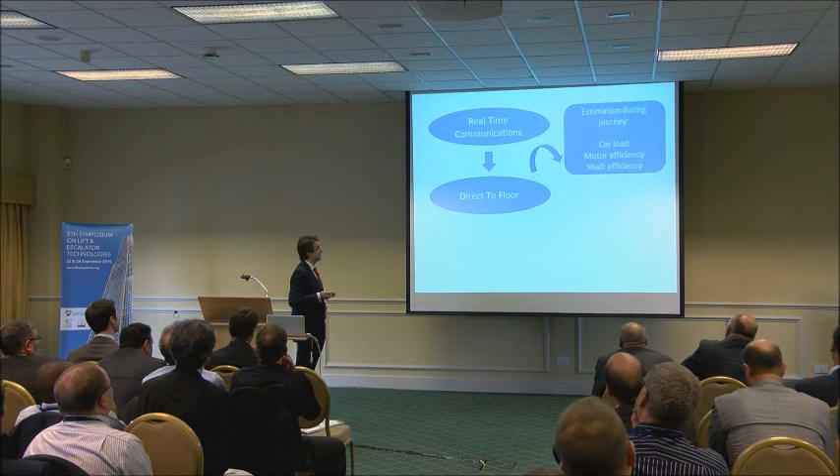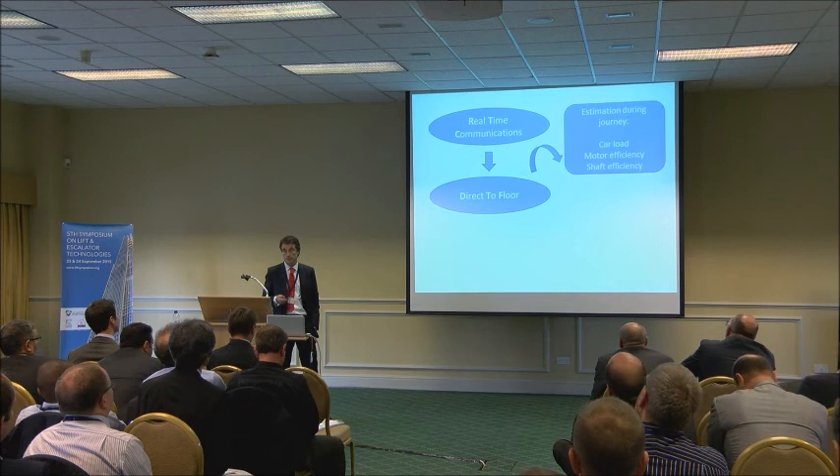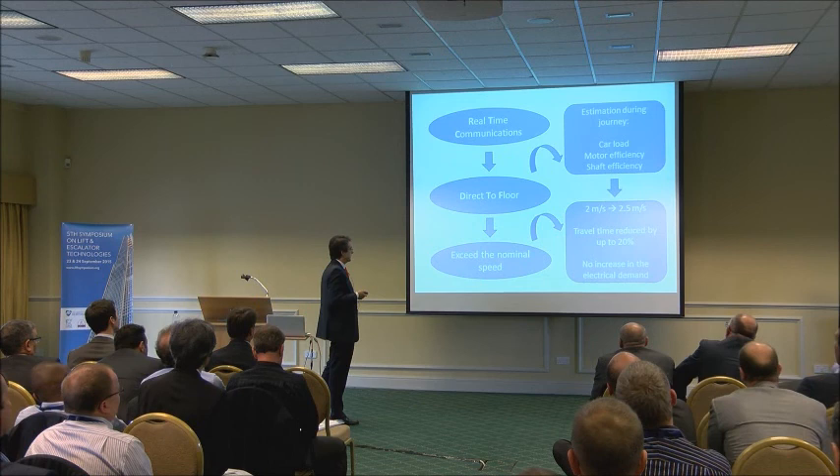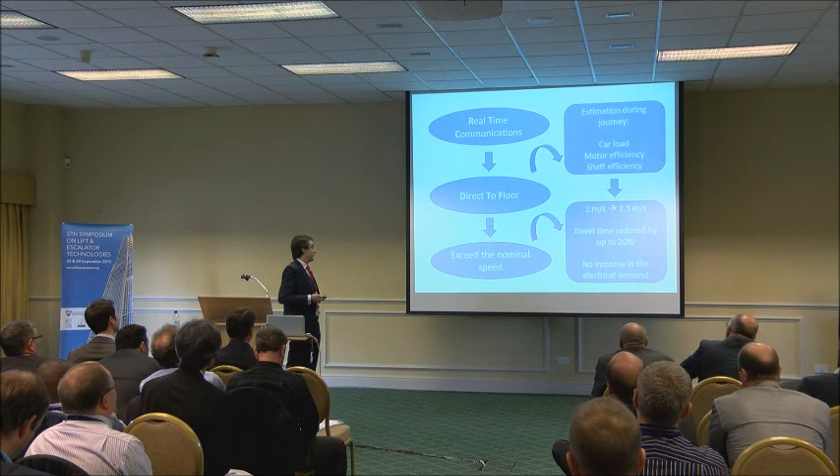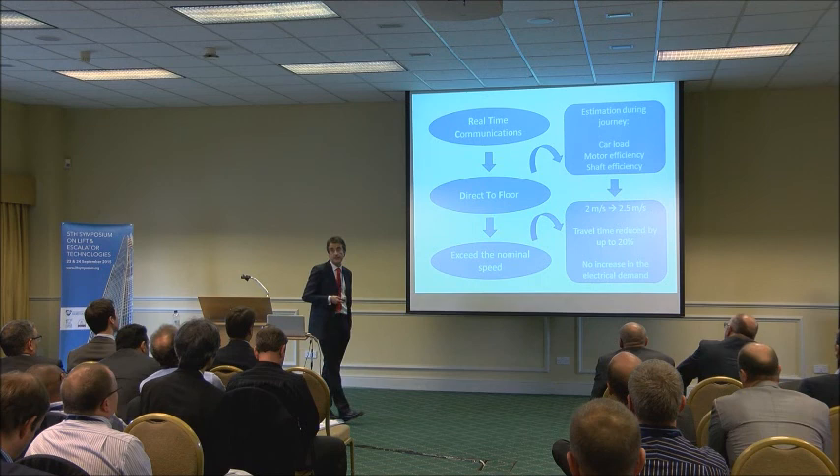So we have real-time communications and direct-to-floor. What happens if we can estimate, because of the real-time communications during the journey, the car load, the motor efficiency, and shaft efficiency? In certain cases, depending on the load in the car, we could overspeed the motor — we could exceed the nominal speed of the motor. For example, we could reach 2.3 meters per second in a lift rated at 2 meters per second. The travel time will be reduced and we shouldn't increase the electrical demand.